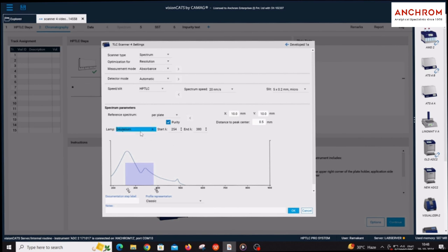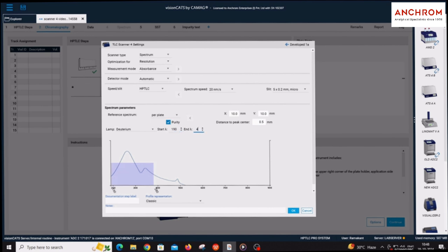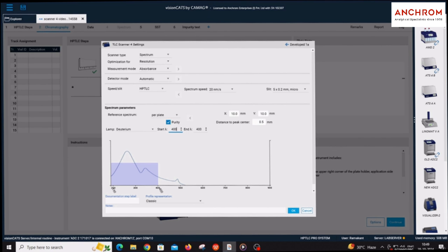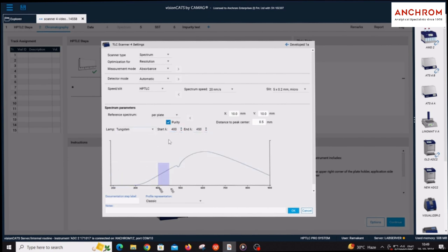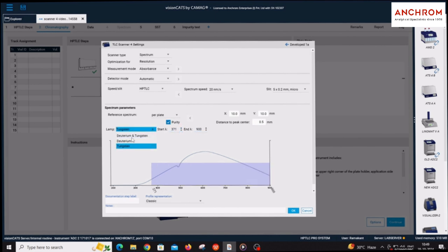If the compound is active in UV light, then spectrum is taken in the range from 190nm to 400nm using a deuterium lamp. If the compound is active in visible light, then spectrum is taken in the range from 400 to 800nm using a tungsten lamp. If the compound is active in UV and visible light, then spectrum is taken in the range from 190 to 900nm using deuterium and tungsten lamps.